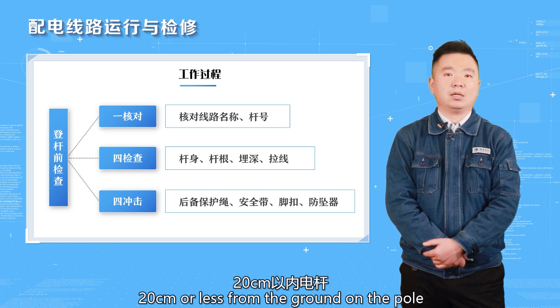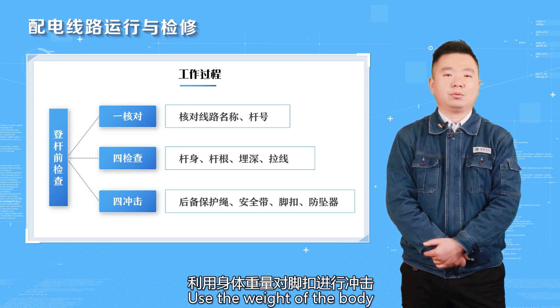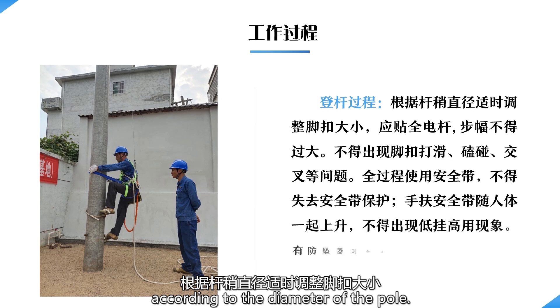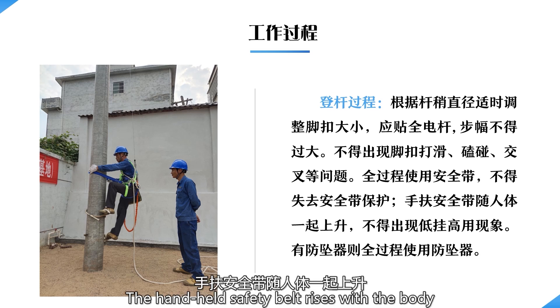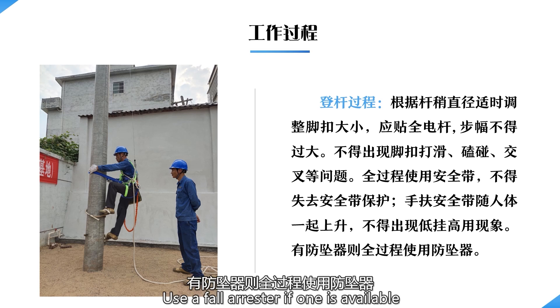During the impact, the whole body should stand on the foot buckle and use body weight to impact the foot buckle with a fall arrester. Boarding process: adjust the size of the buckle according to the diameter of the pole; the foot buckle should stick to the whole pole. The stride shall not be too wide — no slippage of foot buckles or bumping. Use a safety belt throughout; no loss of harness protection. The handheld safety belt rises with the body; the phenomenon of hanging low and using high must not occur. Use a full arrestor if one is available.